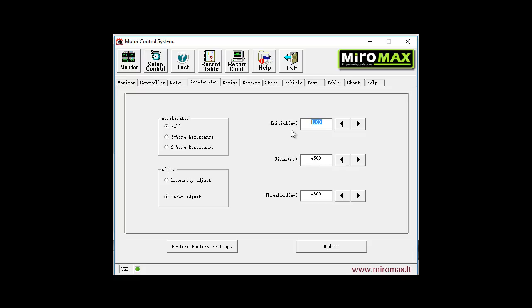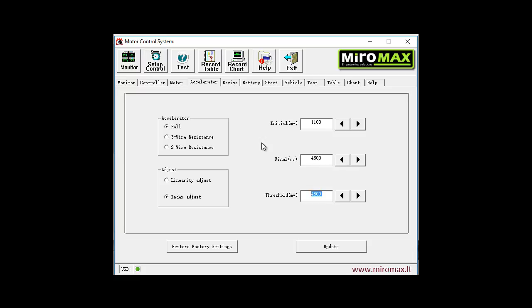Here they are expressed in millivolts. They define speed characteristic starting and ending points: initial millivolts and final millivolts. The first relates to zero point in the speed scale, and the second number relates to 100 percent in the speed scale. The third parameter is protection threshold. It is higher than final and is intended to recognize dangerous situations when something is going wrong, because usually the speed signal shouldn't get too high. But if this happens, then this threshold is set to activate that protection.